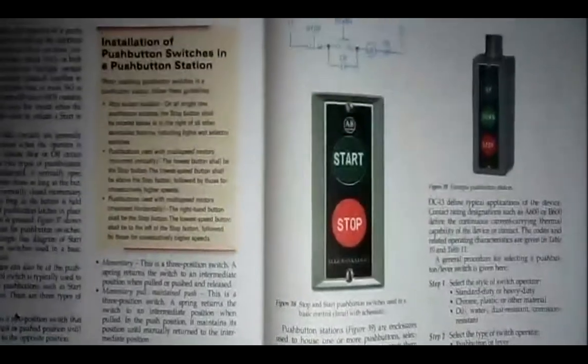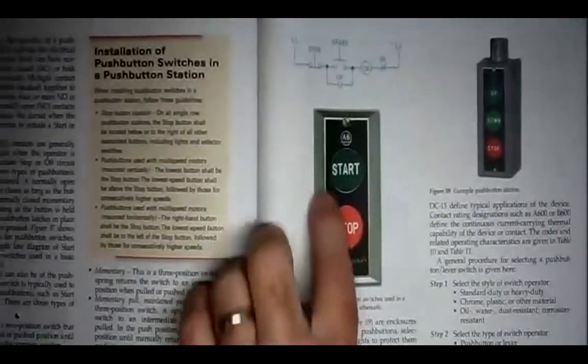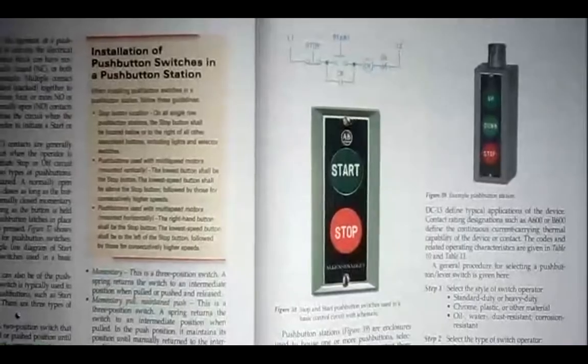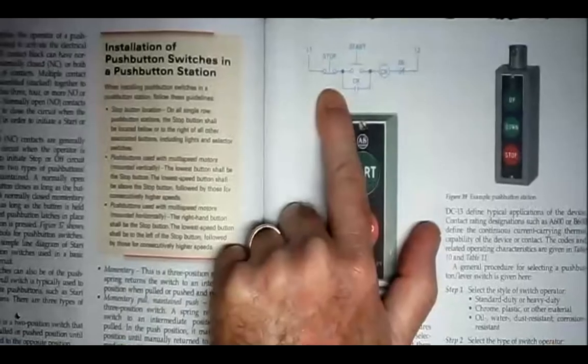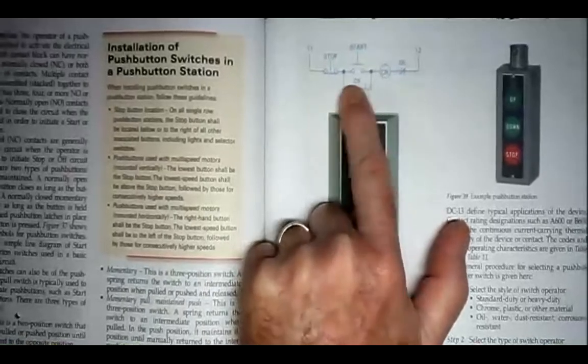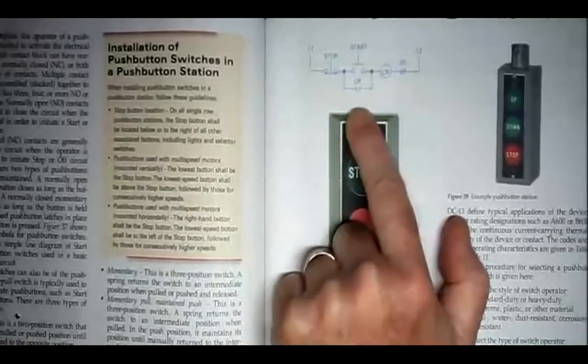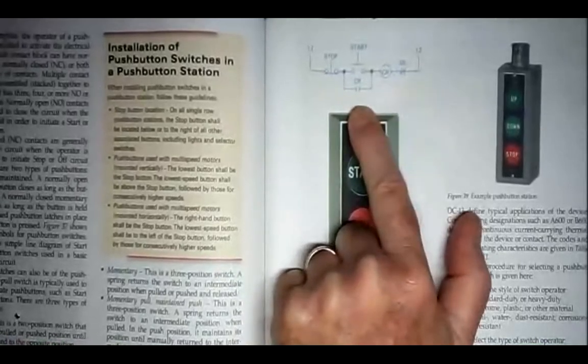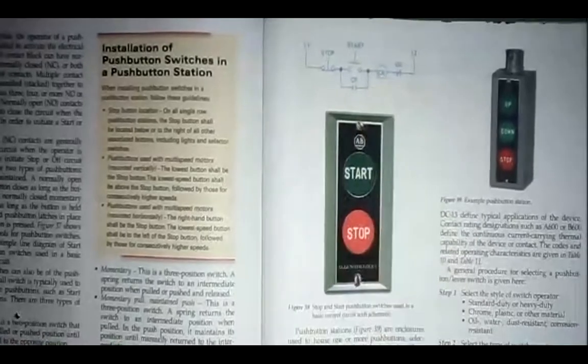All right. And here's a typical start-stop station over on page 37. There's your stop is normally closed, your start is normally open, and it goes to the control relay with a holding contact on the control relay. Okay.